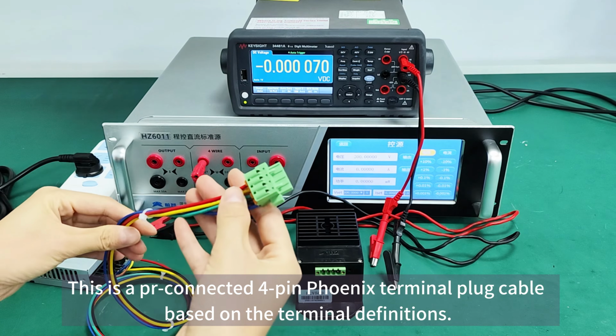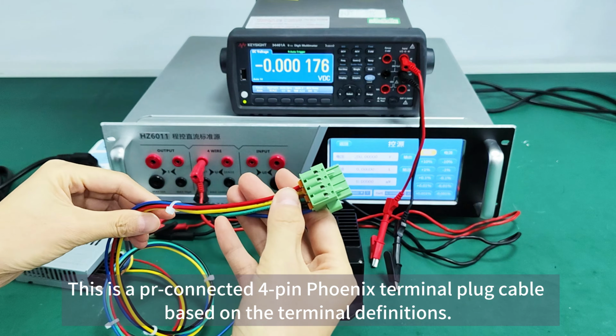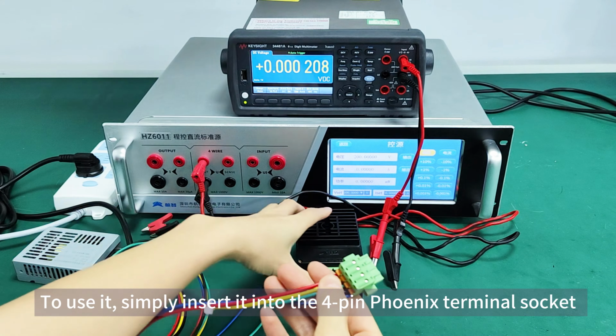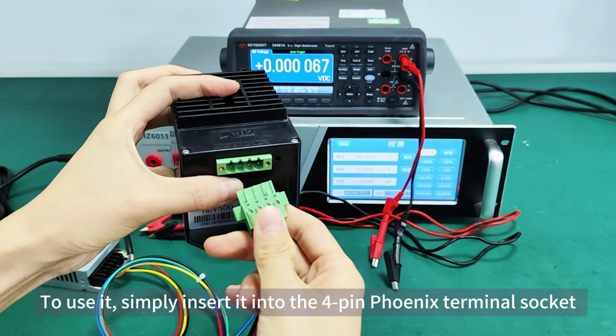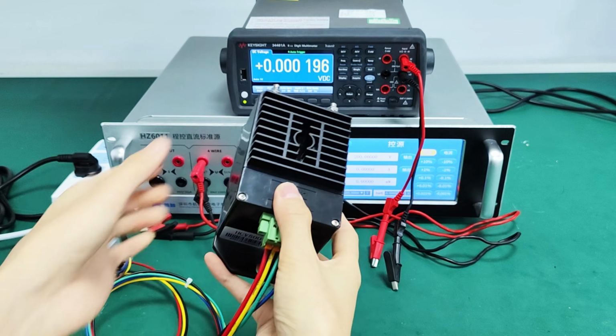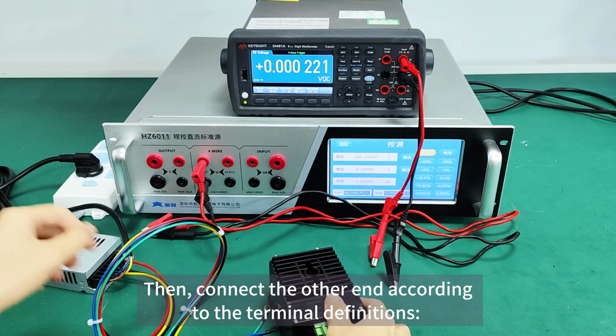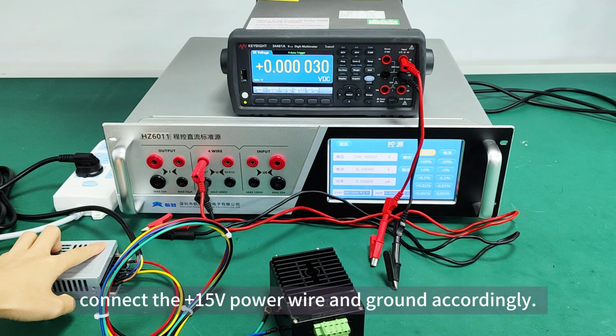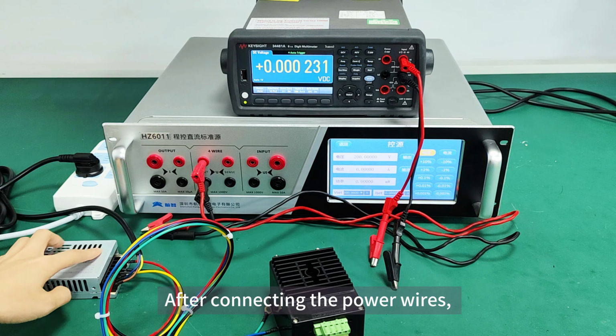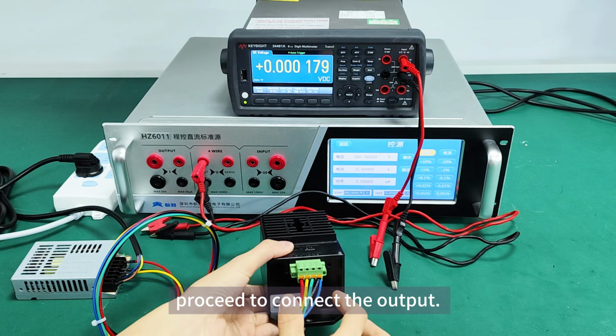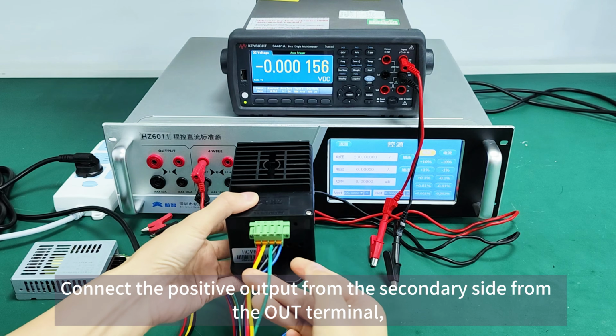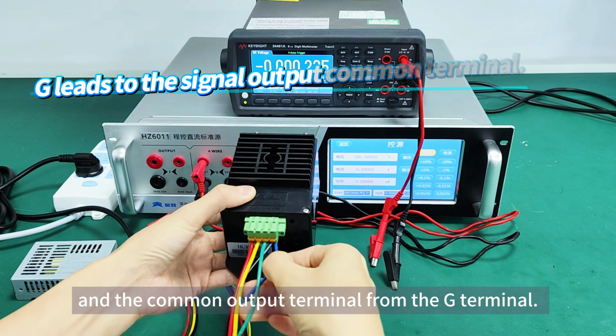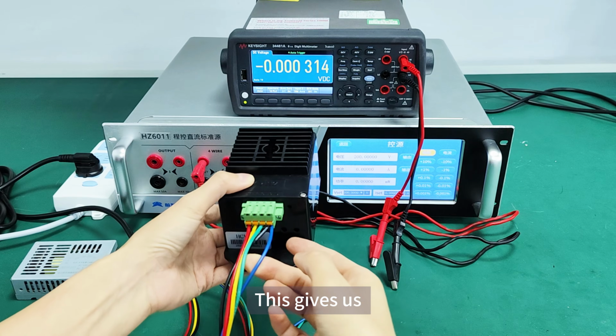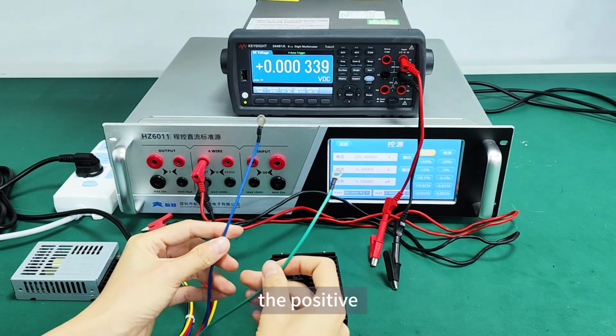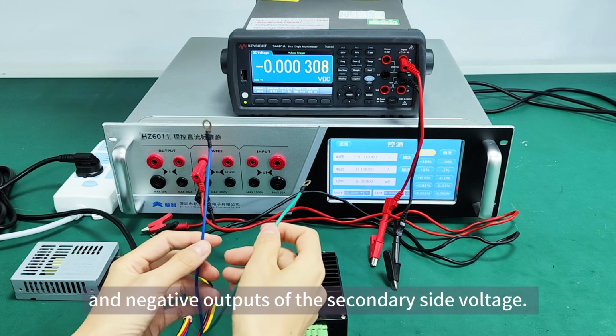This is a pre-connected 4-pin Phoenix terminal plug cable based on the terminal definitions. To use it, simply insert it into the 4-pin Phoenix terminal socket on the transducer. Then, connect the other end according to the terminal definitions. Connect the 15 volts power wire and ground accordingly. After connecting the power wires, proceed to connect the output. Connect the positive output from the secondary side from the out terminal, and the common output terminal from the GND terminal. This gives us the positive and negative outputs of the secondary side voltage.